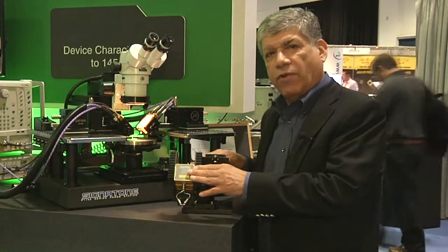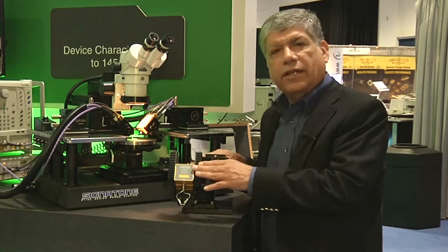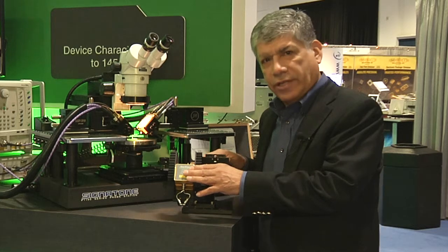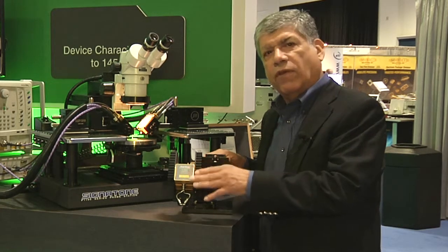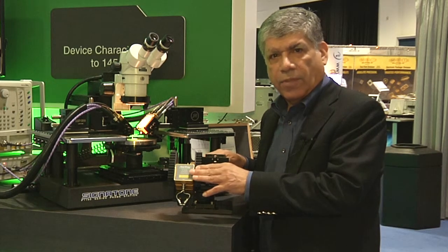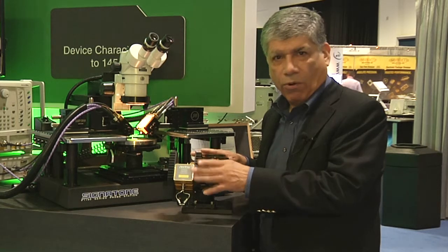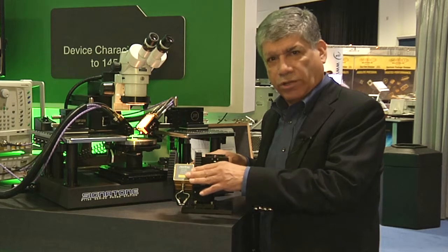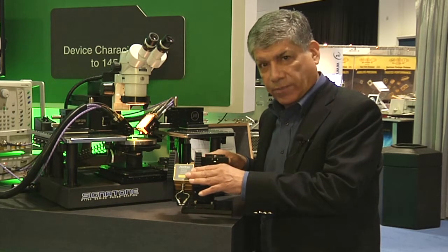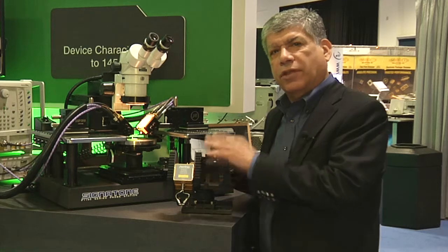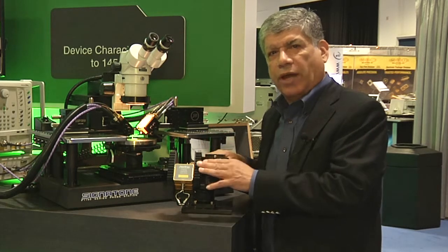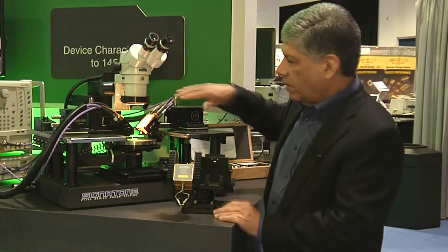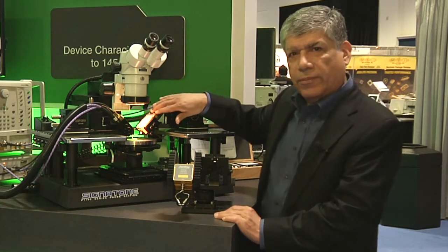And then starting at 54 gigahertz, we multiply the signals up in various bands. So for our standard 110 gigahertz modules, we are going from 54 gigahertz to 80 gigahertz, 80 to 110 or 125 even, in this case for the original nonlinear transmission line modules. Then in order to get to the next band, we add another multiplier band, and we're multiplying from 110 to 145. And that's what these new modules are doing.